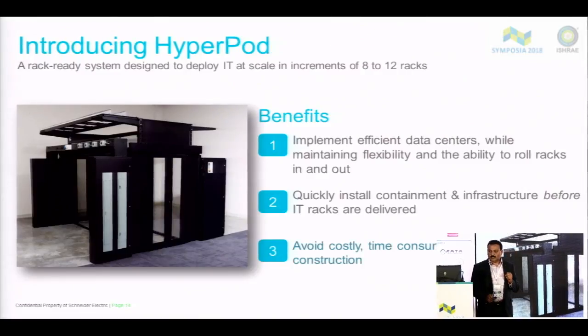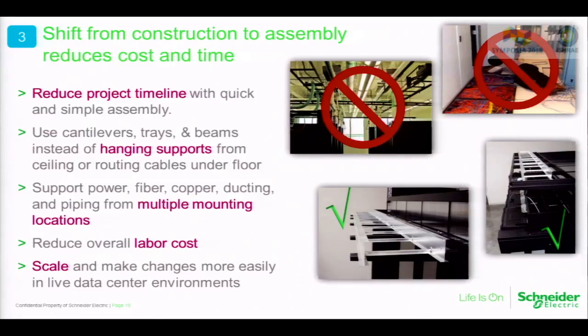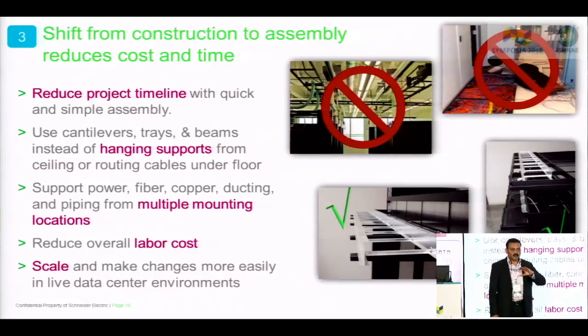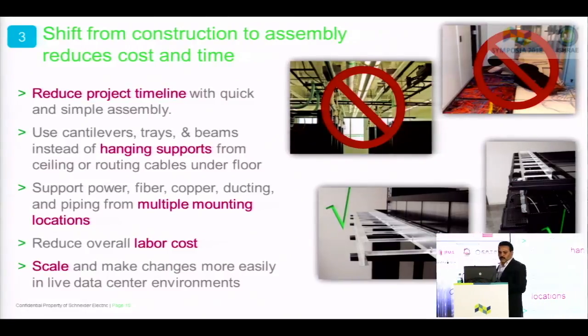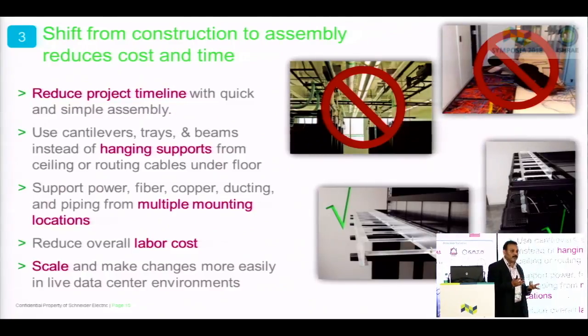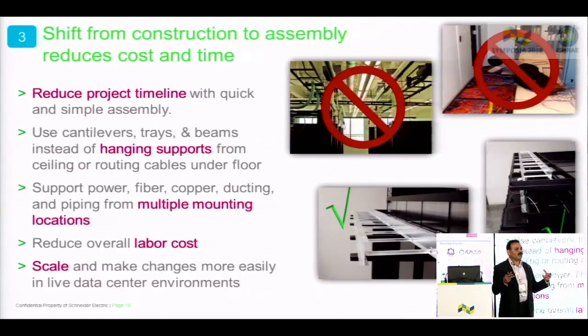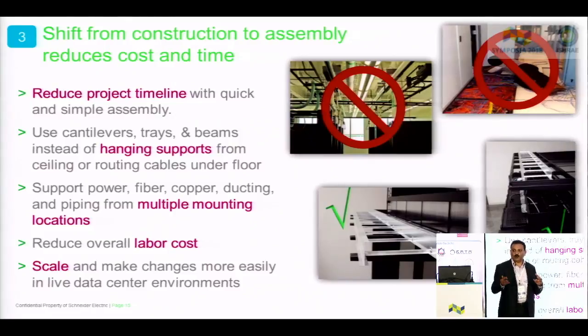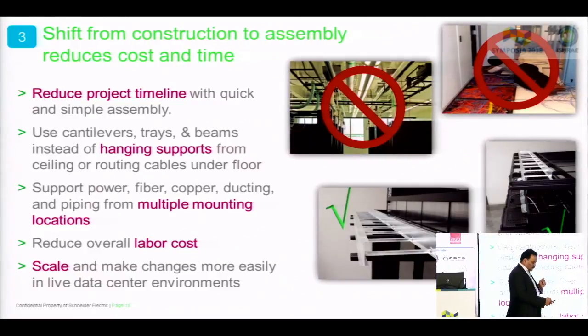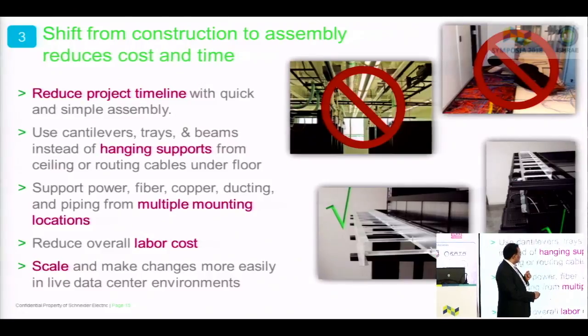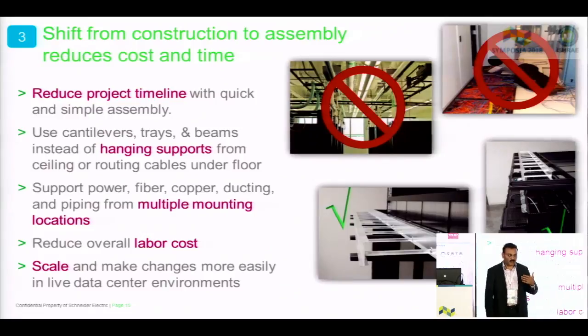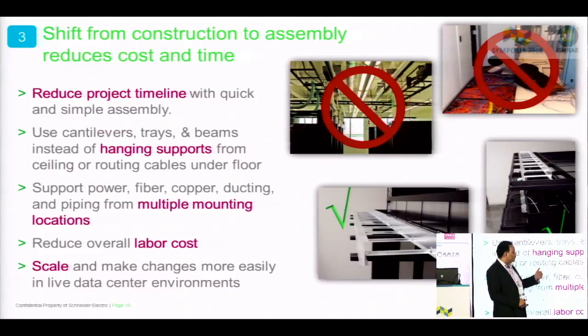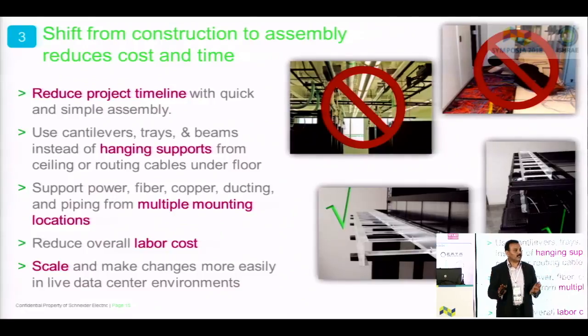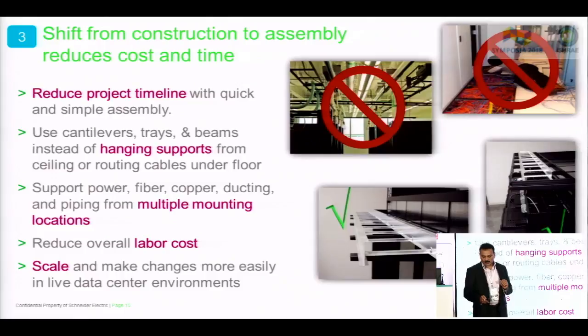Finally, there are a few more benefits. No ceiling suspended cable trays, no cables below the raised floor. It supports power, fiber, copper, ducting and piping. Everything it supports. This is the reason why we call it the backbone of your IT systems in the white space. Now this is something which is absolutely important for us. So you can replace the ceiling suspended cable trays with the trays here, which come as a standard accessory based upon the solutions. For the data cabling, there are separate provisions on the right side. So this becomes an entire infrastructure for your IT equipment in your data center. I'll just take you through a small video and then we'll take this further.